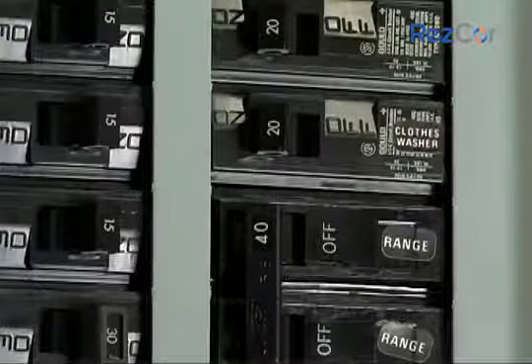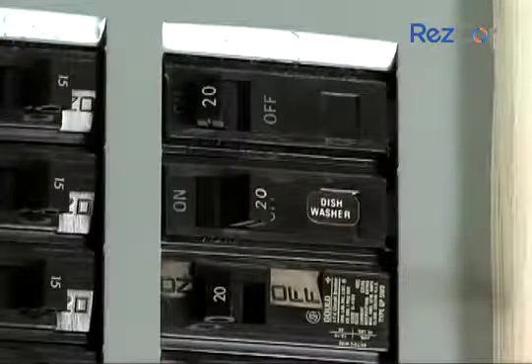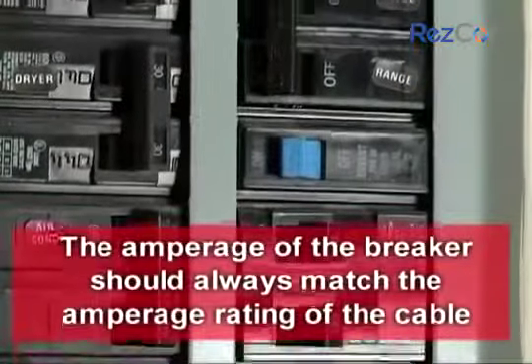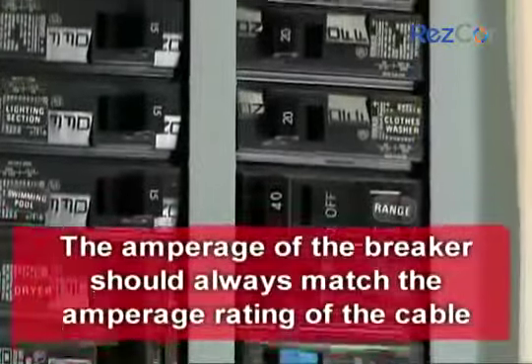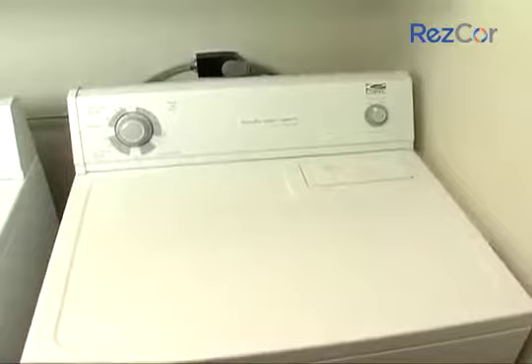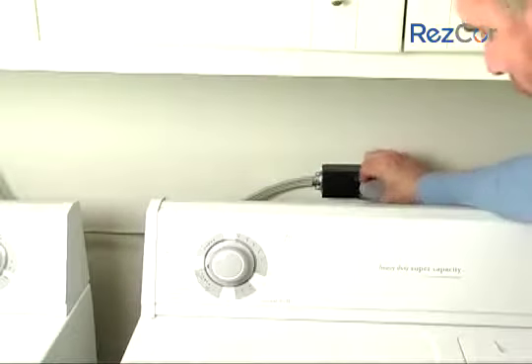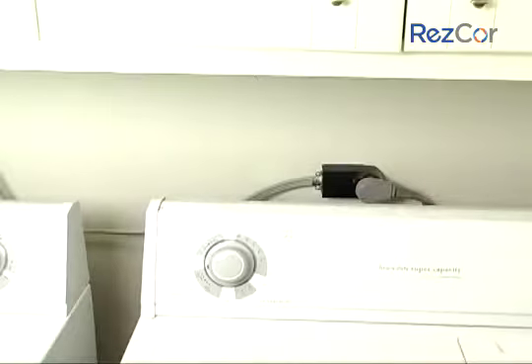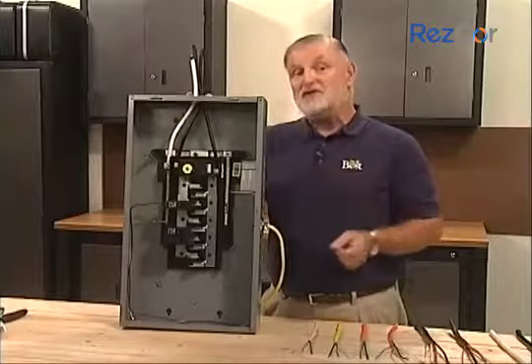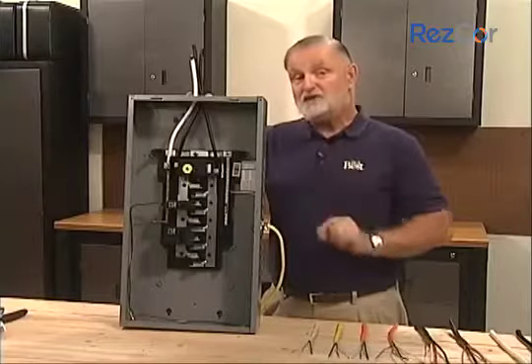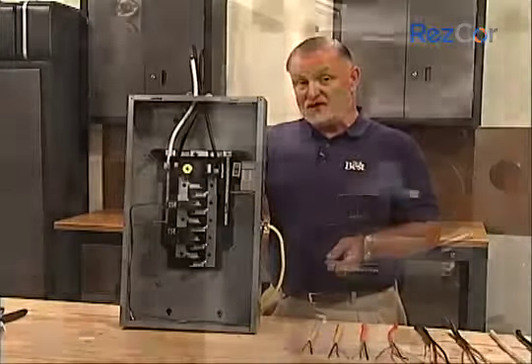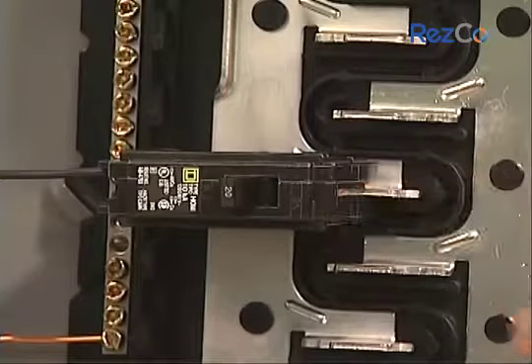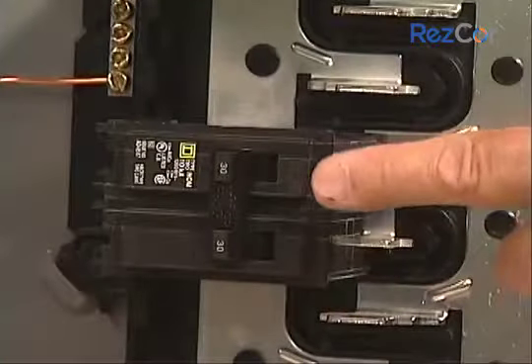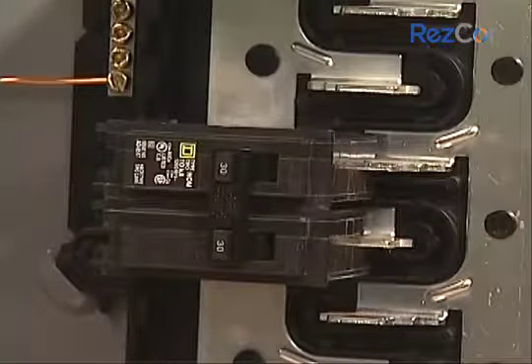Fuses or circuit breakers in the panel box protect the circuits to prevent too much amperage from flowing on the wires. The amperage of the breaker or fuse should always match the amperage rating of the cable. Some electrical appliances such as clothes dryers, electric ranges, and water heaters require more amperage than others. These appliances are known as 240 volt devices because they need two lines of pressure to operate. When you need to connect to your panel to get 120 volts, you use a single pole breaker. When you need 240 volts, you use a double pole breaker, which will automatically connect to both bars in the panel box.